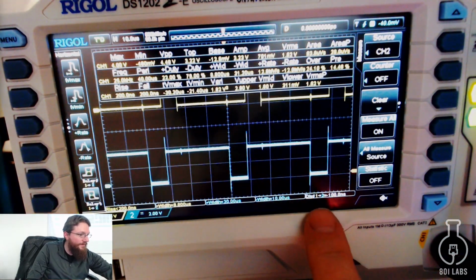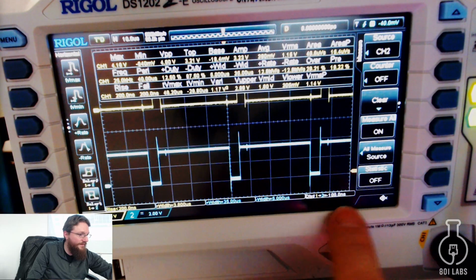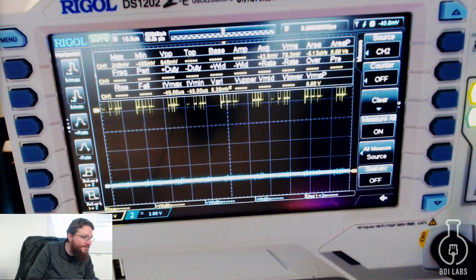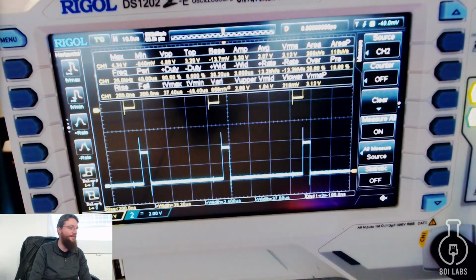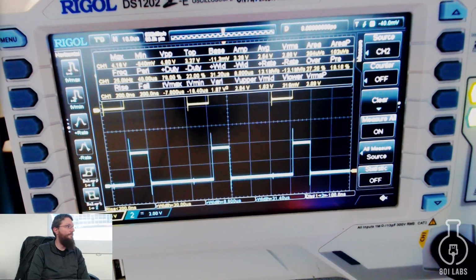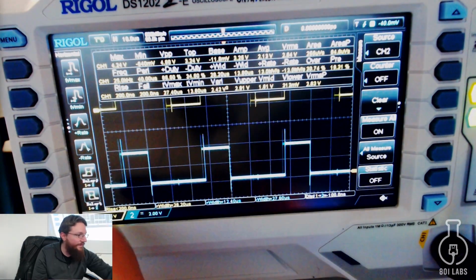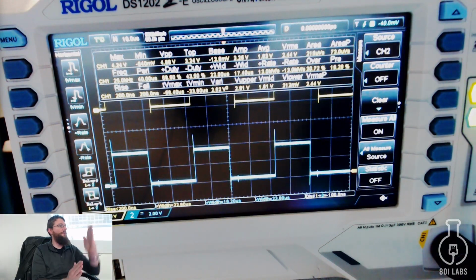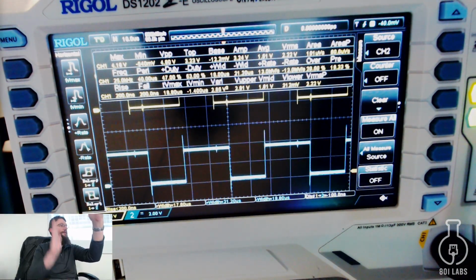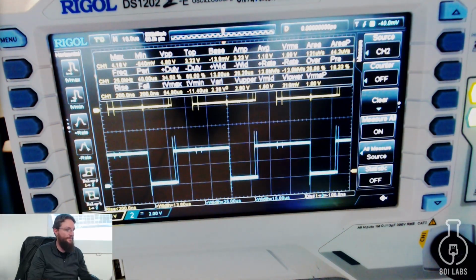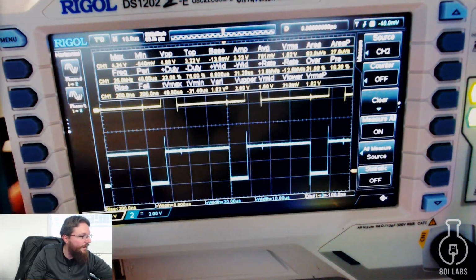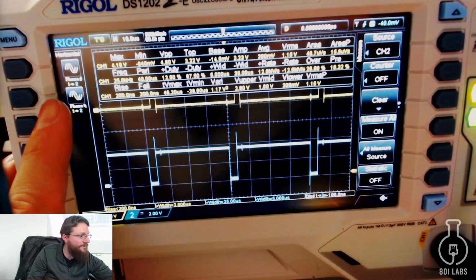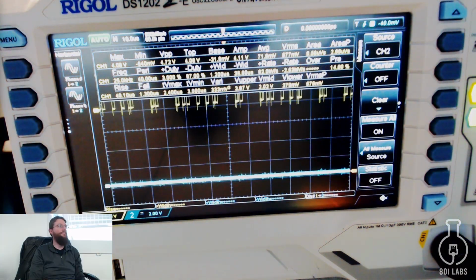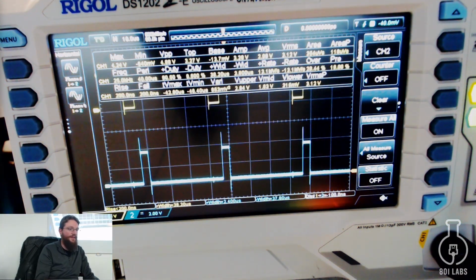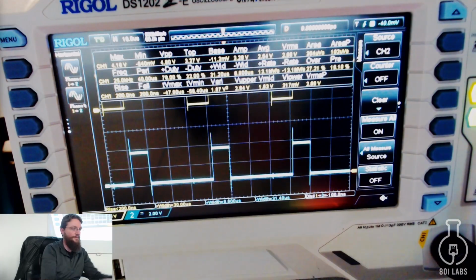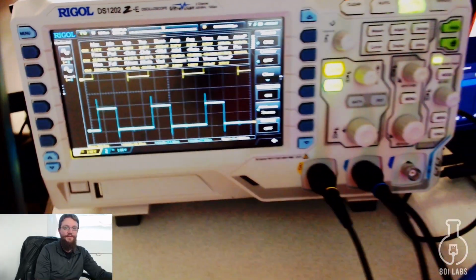Yeah, so the delay between 1 and 2 is 100 nanoseconds, and it stays that way as long as they're both on. Is that signal 1 or signal 2? Yeah, so it's the rise. This is measuring the delay between signal 1 rising to the next time signal 2 rises. And then you can also do phase measurements for AC voltages. If none of this is good enough for you, I'm going to zoom back out.